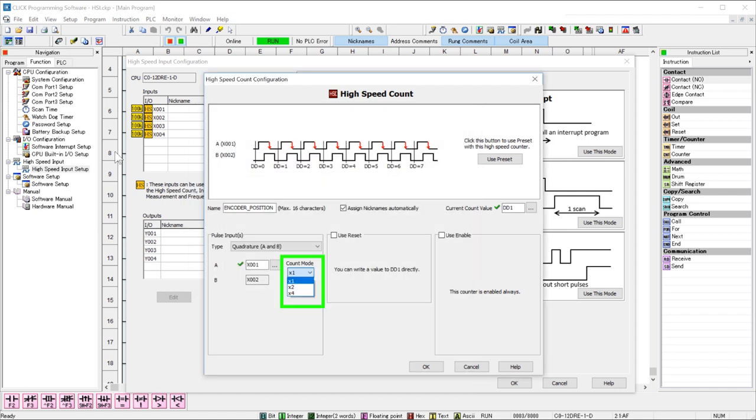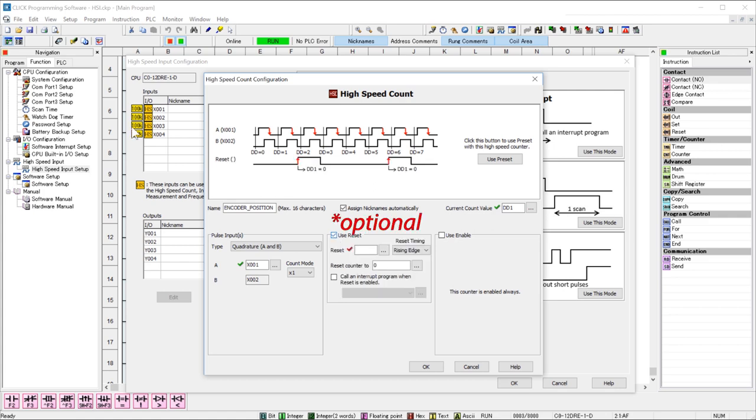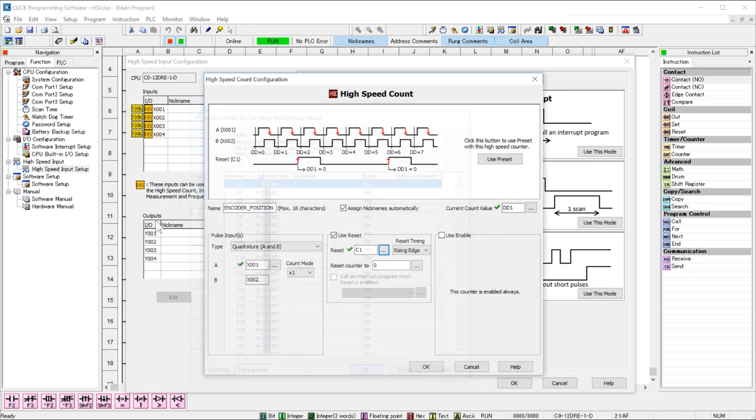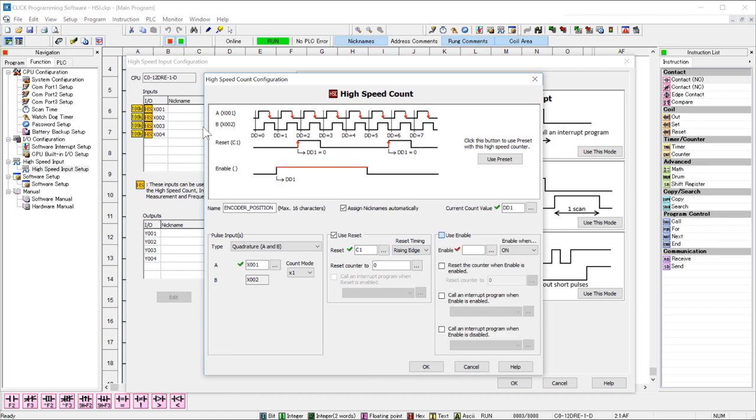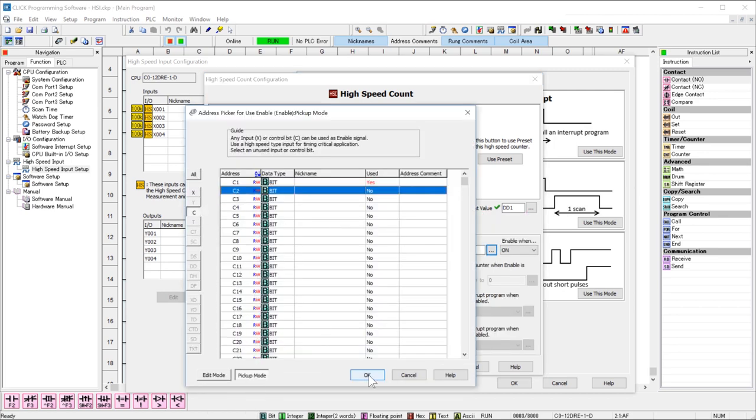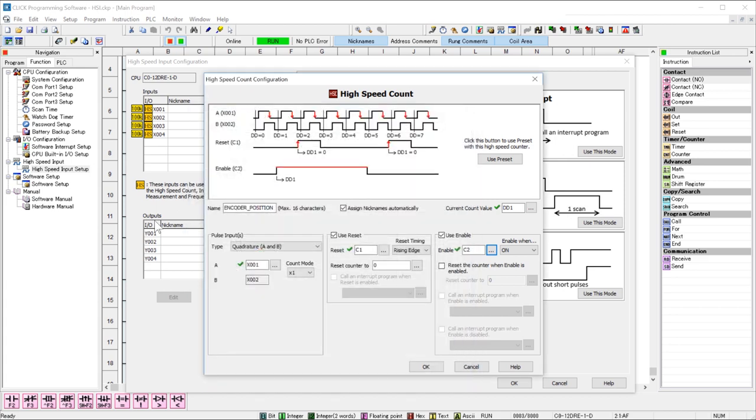This will allow you to put a multiplier on the count. Here are your reset options. I will assign the internal coil of C1. If you use an internal coil instead of a hardwired input, realize that this will be dependent upon the scan time. This option allows you to enable the count or disable the count based upon the status of a bit.